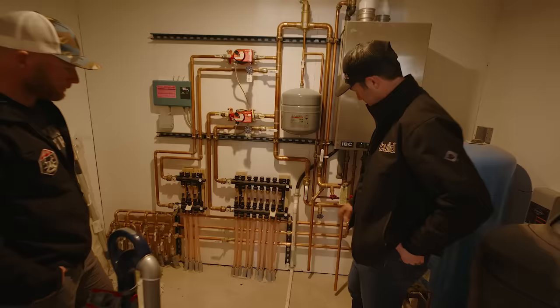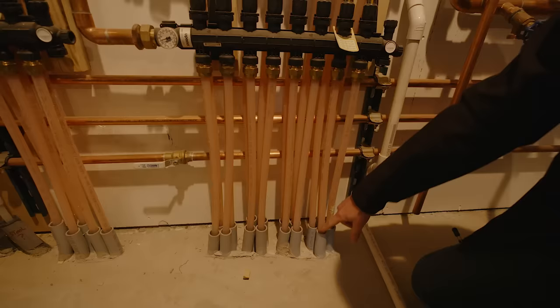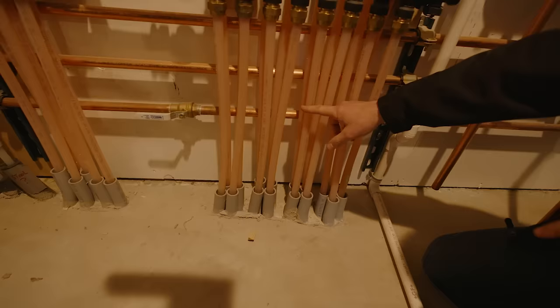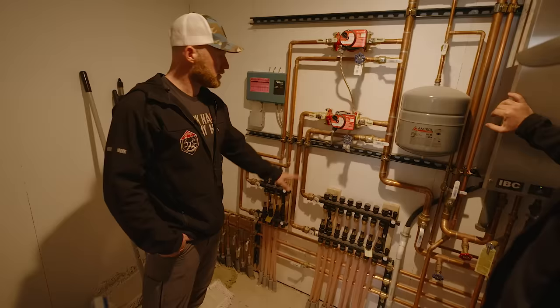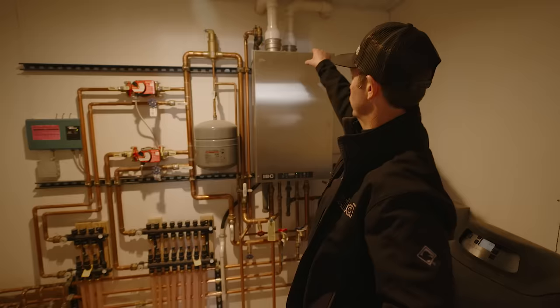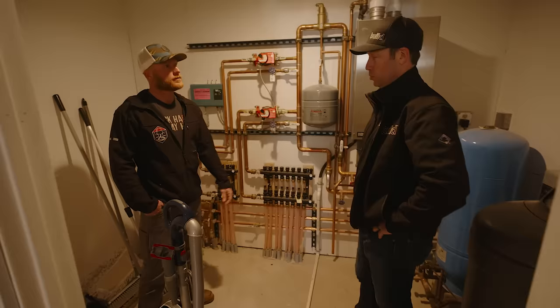There's a mechanical room right here. The guys that did it did a really good job. Looks like Uponor PEX coming up through a radiant system on the floor with sleeves in. The pink color means it's glycol-filled, not water — so in case of an issue, it's not going to freeze. It has a much lower freeze point than water. He's got a Uponor system for all his controls. Clean lines, nice clean solder joints — the plumber did a real nice job. This is your boiler with a direct vent to the outside.